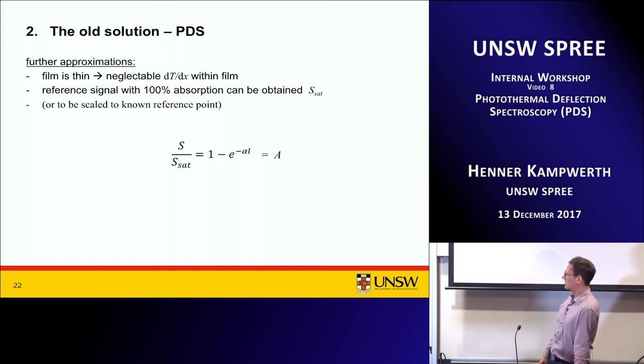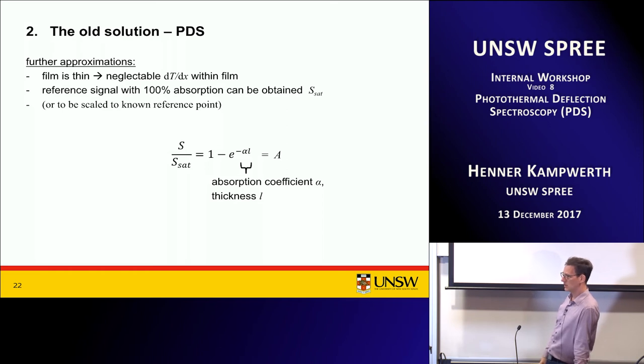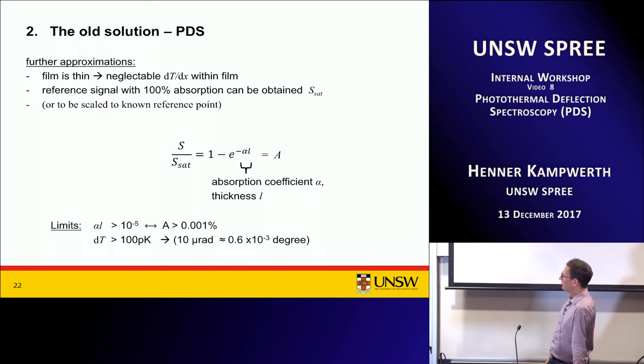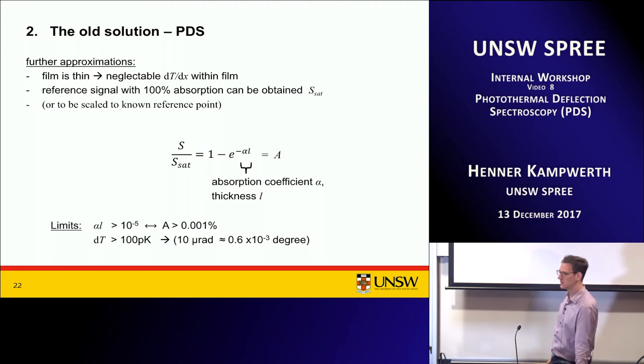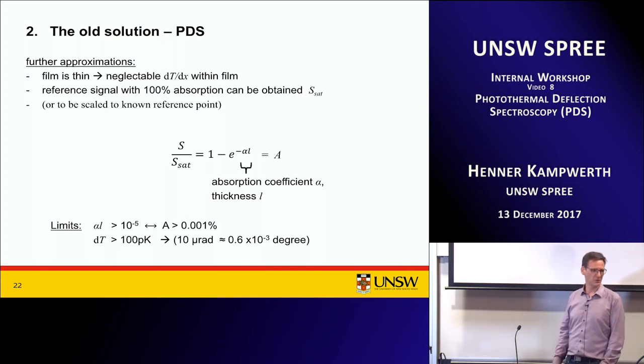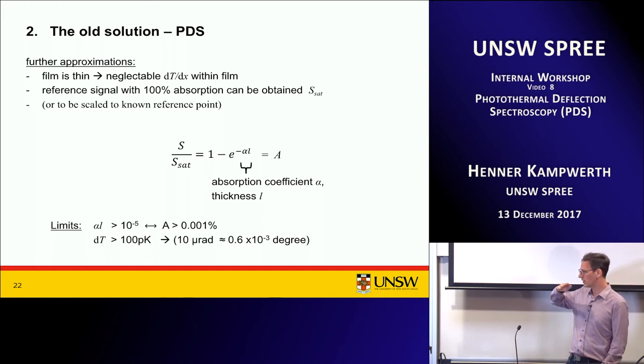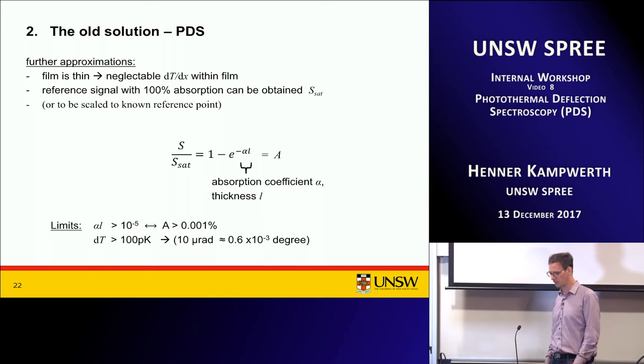The absorption limit calculates out to 0.001% compared to 0.5% for the R&T technique — significantly more sensitive. For those interested in the technical side: the temperature difference of the material you can measure is only 100 pico-Kelvin, which is probably the most sensitive temperature detection I've come across. And the beam is deflected by only 0.6 milli-degrees, which is also very, very little.